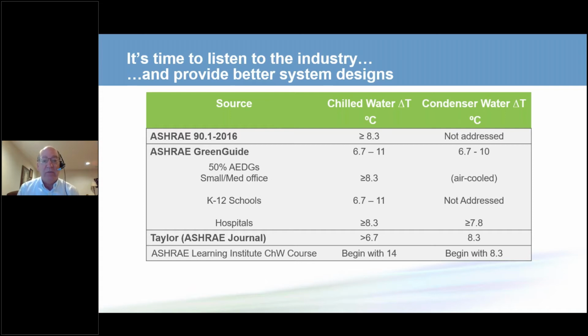ASHRAE Standard 90.1, starting in 2016 and 2019, requires coils to be selected with at least a 15 degree delta T, which is 8.3 degrees C delta T. And that's higher than it was in the past. The ASHRAE Green Guides all recommend higher delta Ts and lower flow rates, both on the chilled water side and the condenser water side.